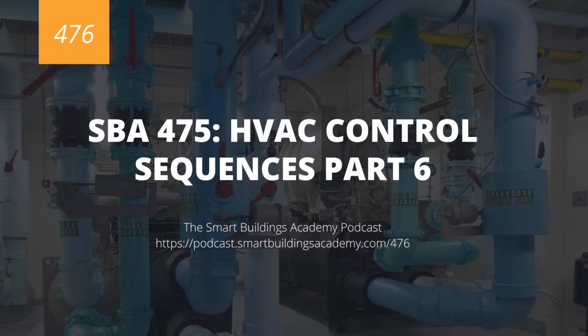Now, if you followed my podcast for a while or you've been through our BAS programming bootcamp, then you know I'm a big fan of state-based control. I believe that you should utilize state-based control and you should have logic that is commanded based on state. So you should have a cooling enable state, a heating enable state, and your logic should do specific things based on the state it's in. This way, it's easier to troubleshoot because you know what state you're in, you know what things should be doing, and it keeps things from just being crazily intermixed and confusing. So our system enable is our state enable for chilled water.